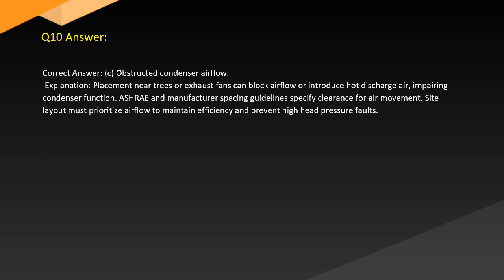Answer. Correct answer: C. Obstructed condenser airflow. Explanation: placement near trees or exhaust fans can block airflow or introduce hot discharge air, impairing condenser function. ASHRAE and manufacturer spacing guidelines specify clearance for air movement. Site layout must prioritize airflow to maintain efficiency and prevent high head pressure faults.